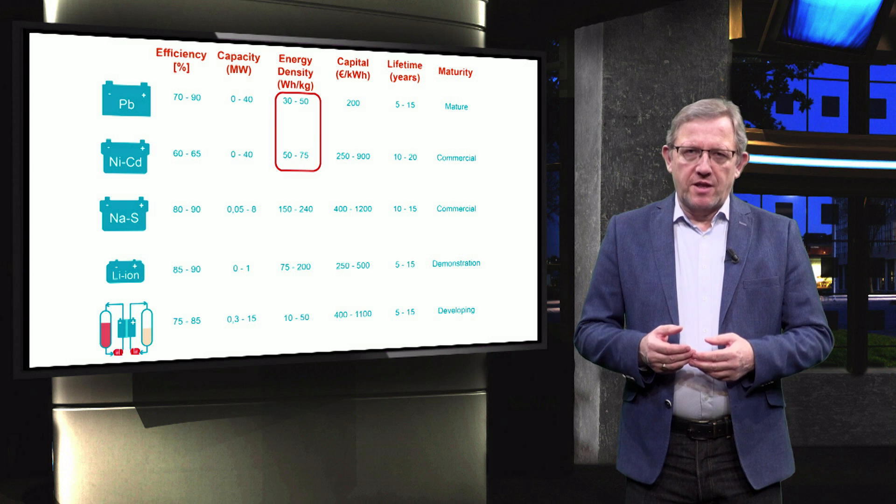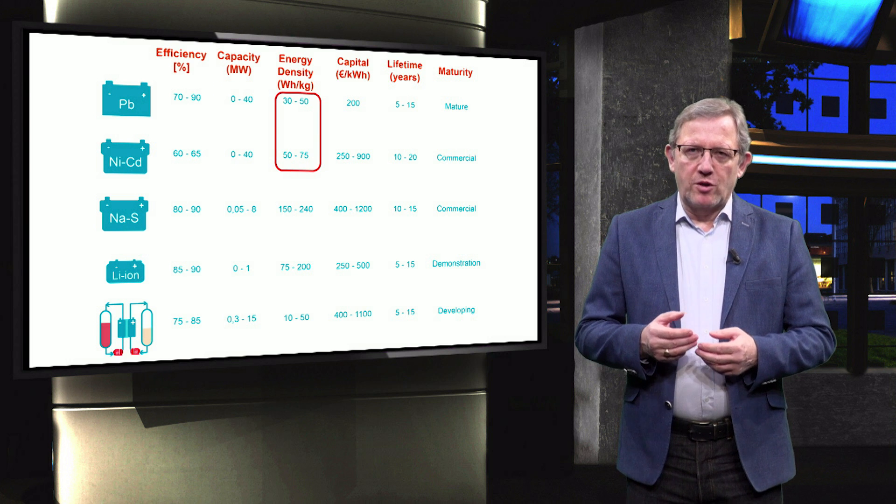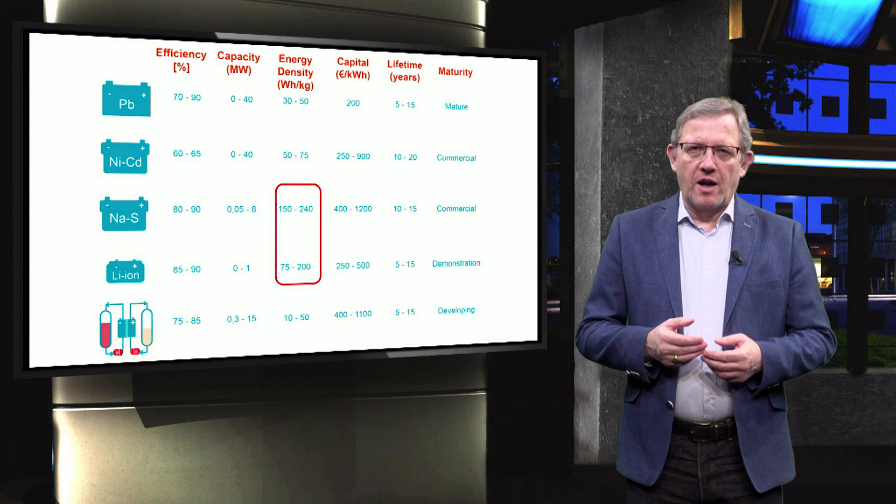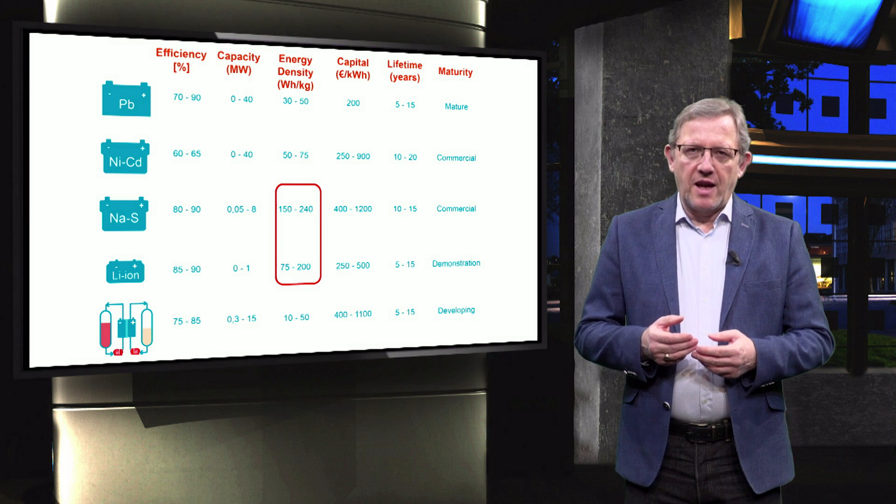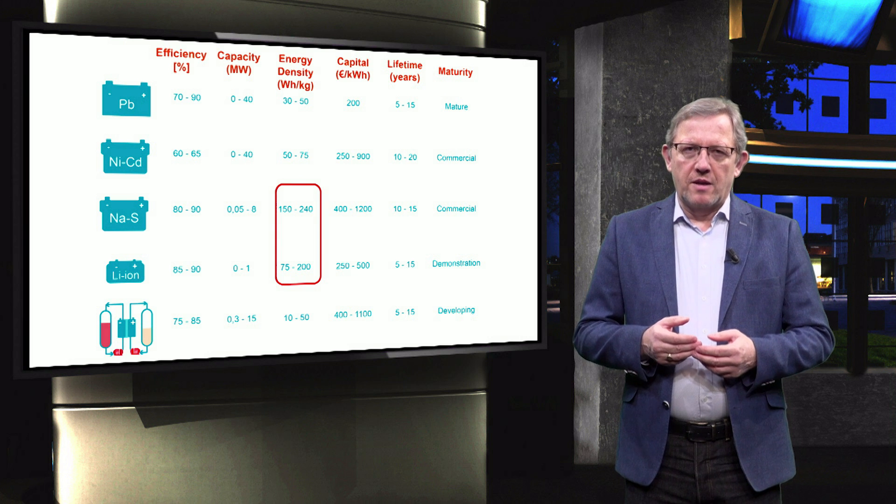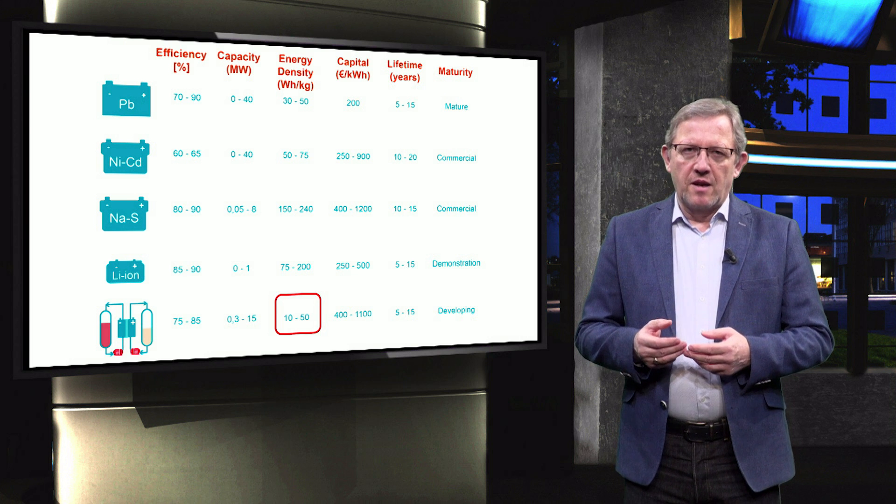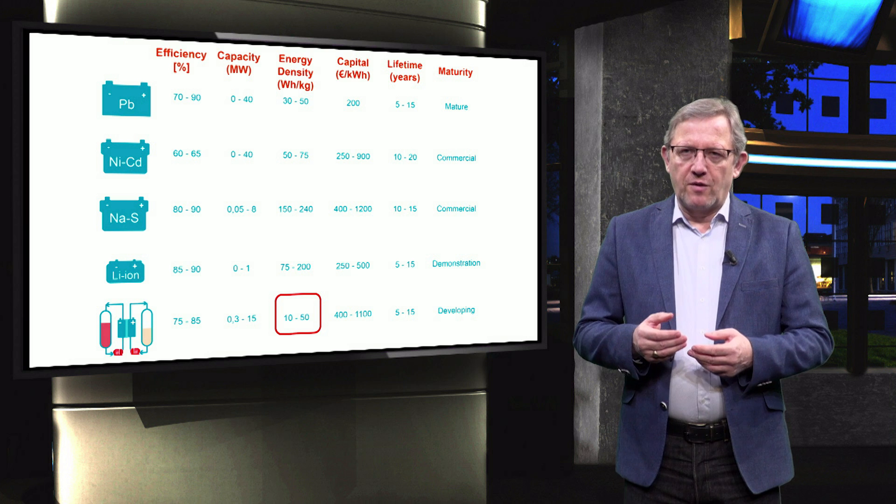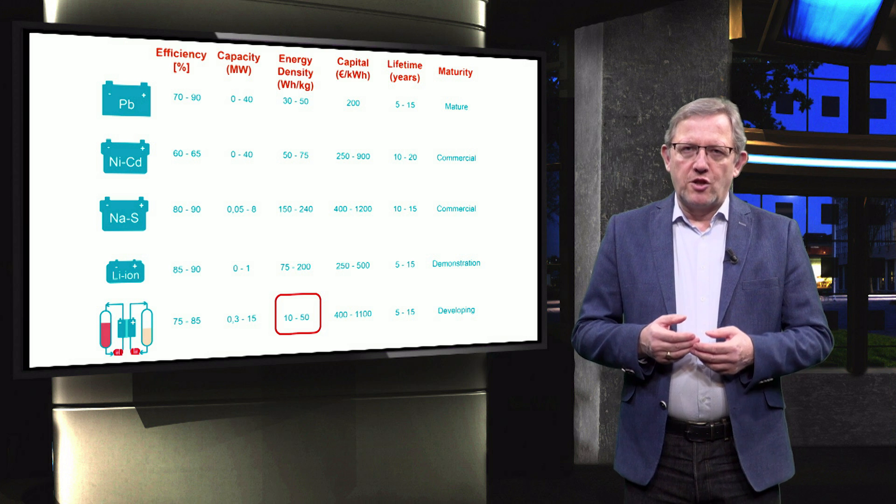Energy density of lead acid and nickel cadmium are moderate, while sodium sulfur and lithium ion batteries have a high energy density up to 240 watt-hour per kilogram. The energy density of flow batteries largely varies between 10 and 50 watt-hours per kilogram.